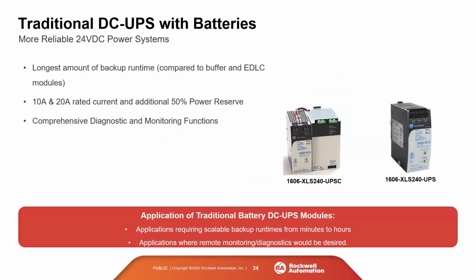And then you have your traditional DC UPS with batteries. These provide you with the largest amount of backup runtime, with 10 amp and 20 amp rated current, and an additional 50% power reserve. In the picture, the first part number on the left is actually a configured part that Rockwell offers, so the UPS plus the battery comes configured and ready to go. But you can also get just the UPS and buy the battery separately, so depending on what you need, you can tailor that.